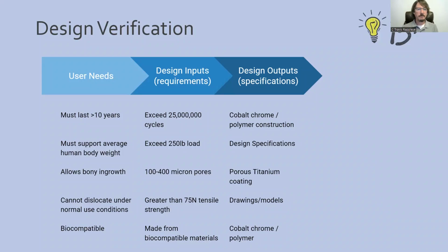And so this is documenting our design in three steps, going in stepwise from the physician giving some input into what their needs are, but not getting specific about the detail. We dig up the details and establish design requirements, design input, list them right next to the user needs. And then once we've invented or designed our product, we have a list of design outputs, which are specifications.